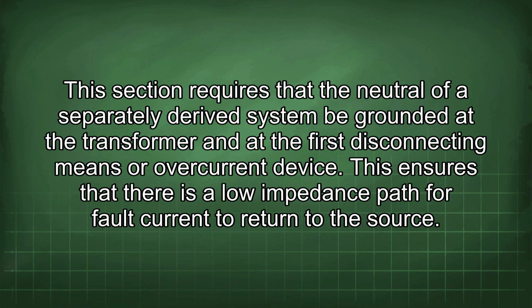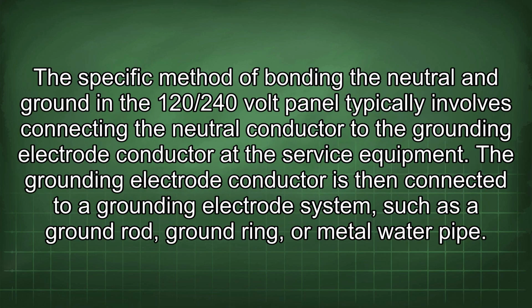This section requires that the neutral of a separately derived system be grounded at the transformer and at the first disconnecting means or overcurrent device. This ensures that there is a low impedance path for fault current to return to the source. The specific method of bonding the neutral and ground in the 120/240 volt panel typically involves connecting the neutral conductor to the grounding electrode conductor at the service equipment.